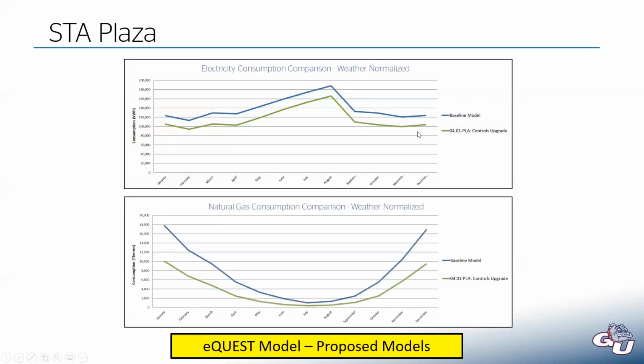On the gas side, the same thing. And you can see, that is a drastic reduction in gas use. And that is virtually entirely owed to that demand control ventilation strategy to reduce the outside air based on the CO2 levels in the space.